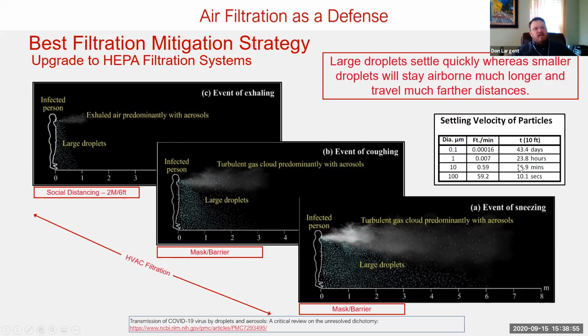Again, this is in a controlled room, no thermal air gradients, no forced air ventilation. It's just a stagnant room. If I had a particle size of 0.1 micron, basically it's going to have a settling velocity of 0.00016 feet per minute. It would take 40 days for it to settle 10 feet.